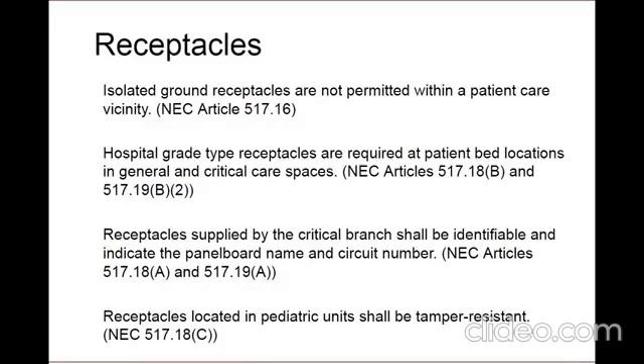Isolated ground type receptacles are not compatible with the grounding requirements in the patient care vicinity. Since the equipment grounding terminal is isolated from the metal mounting yoke, the raceway grounding path is not available to equipment supplied by the receptacle as the ground fault current path. In previous code cycles, isolated ground receptacles were prohibited entirely from healthcare facilities. The 2014 edition revised this, and NEC 517.16 precludes their use in the patient care vicinity. Use is permitted in other areas such as a nurse station.